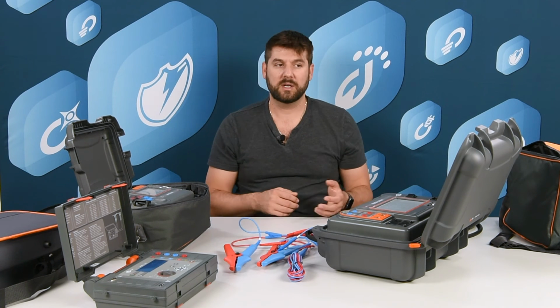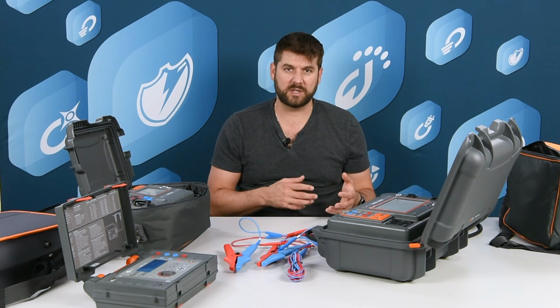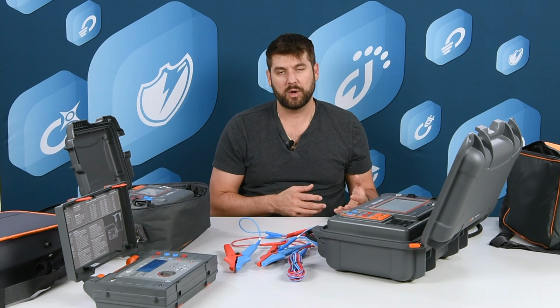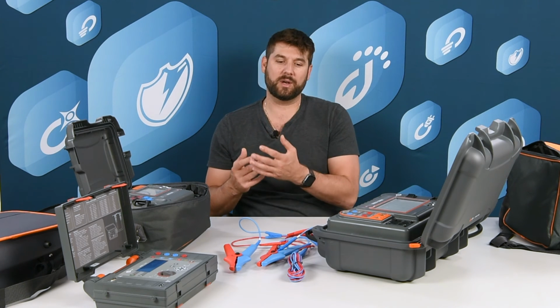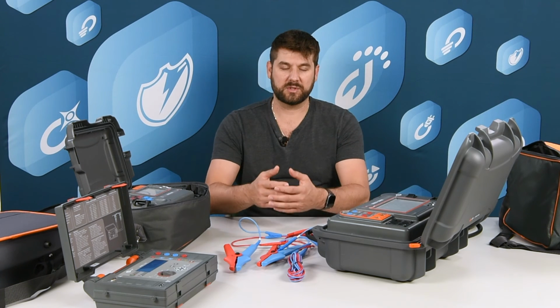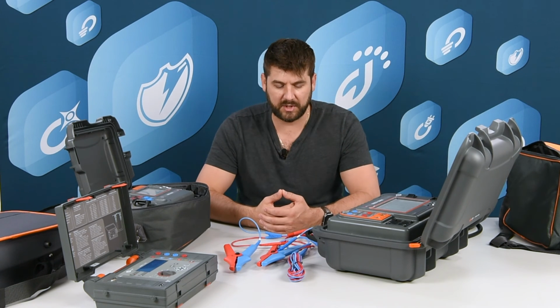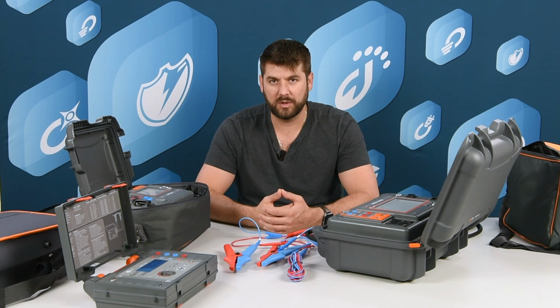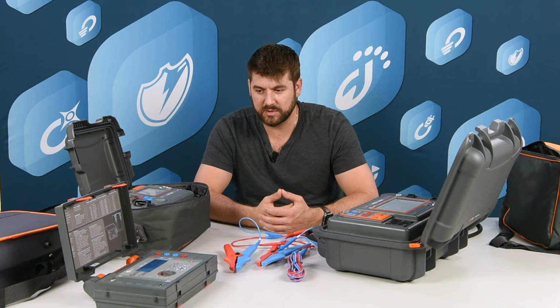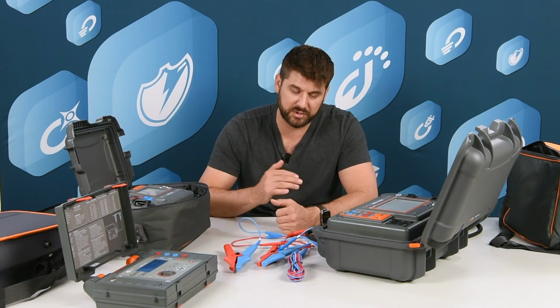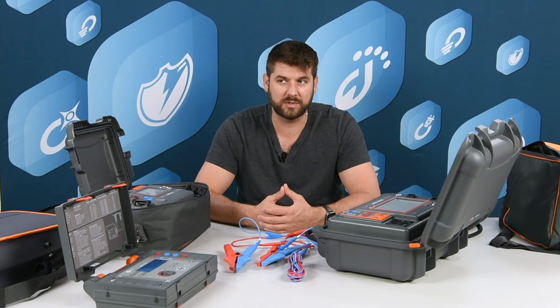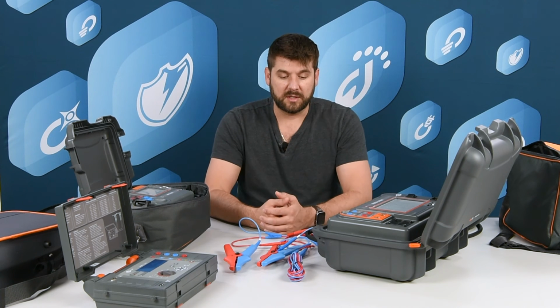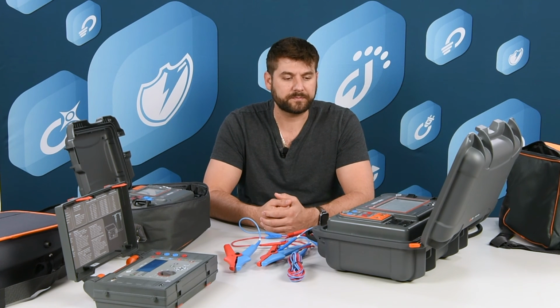And actually, when you disconnect the leads, the depolarization of the core will build voltage back up onto the winding. So you'll have voltage just appearing back on the test object. So whenever you're doing a DC test on a coil, whether it's insulation resistance or contact resistance, if you're pushing DC through a coil, you need to discharge and demagnetize afterwards. Something to be aware of. These instruments will do this, but you should pay attention to it.